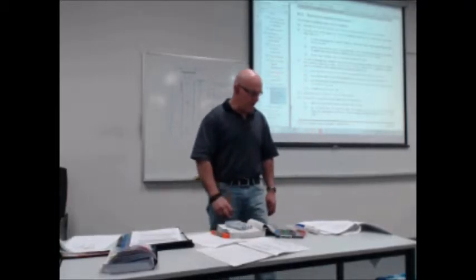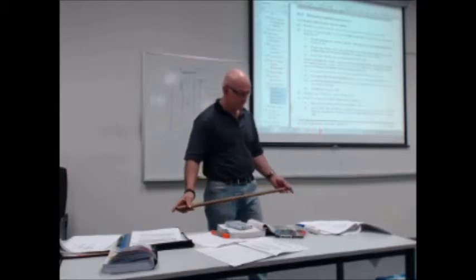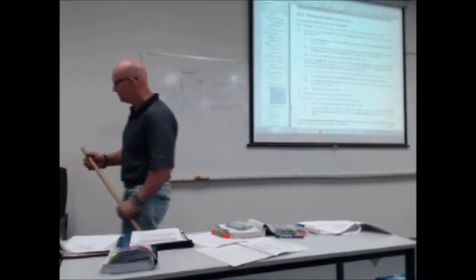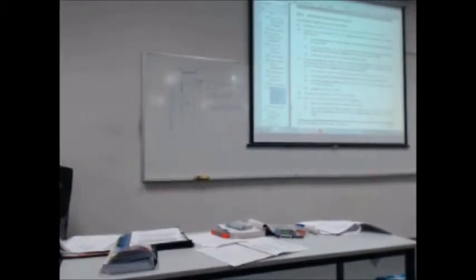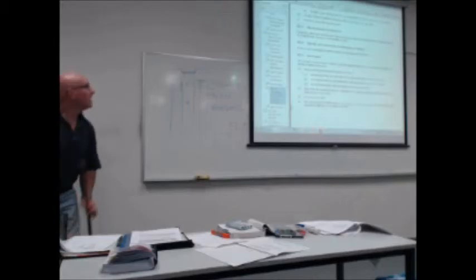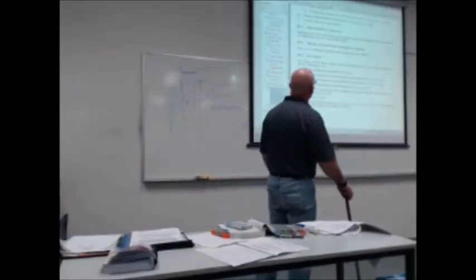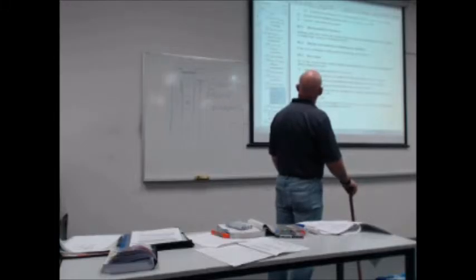Are exit signs required for this building? If so, where? Go to the exit sign section, E4.5. Exit signs must be clearly visible to persons approaching the exit and must be installed on, above or adjacent to each door providing direct egress.